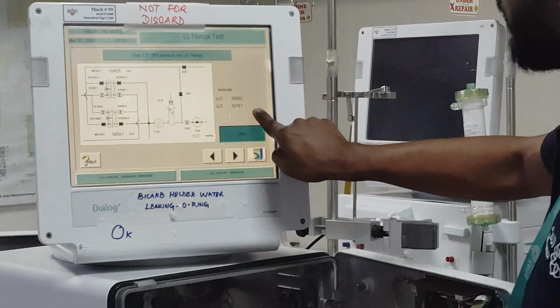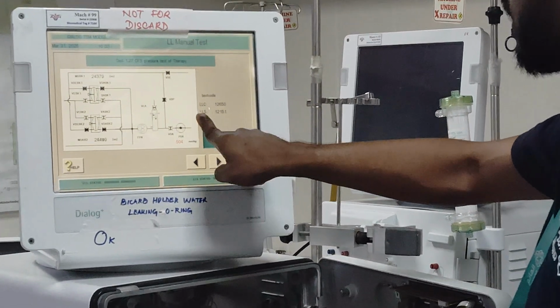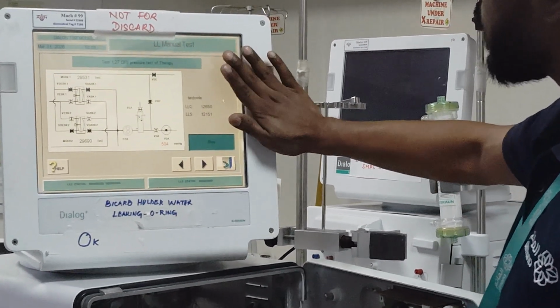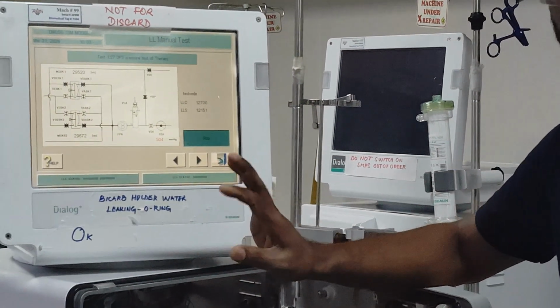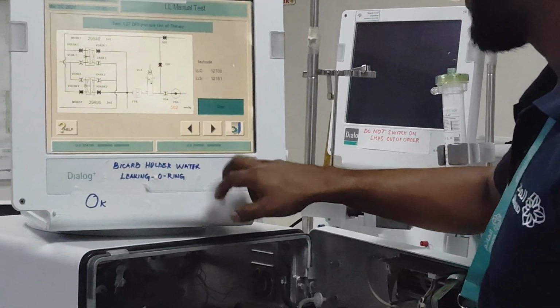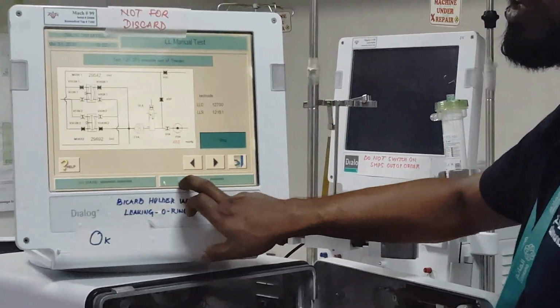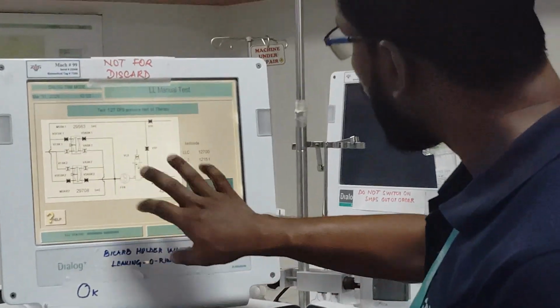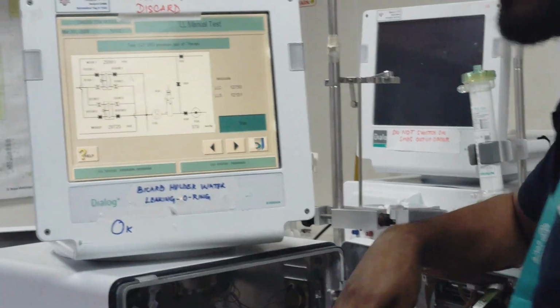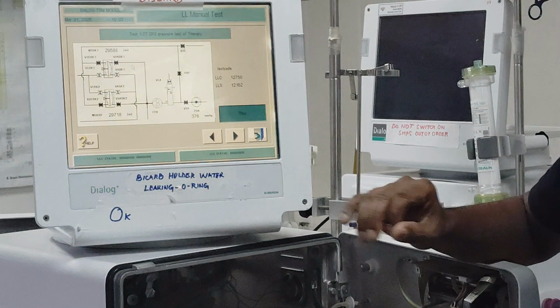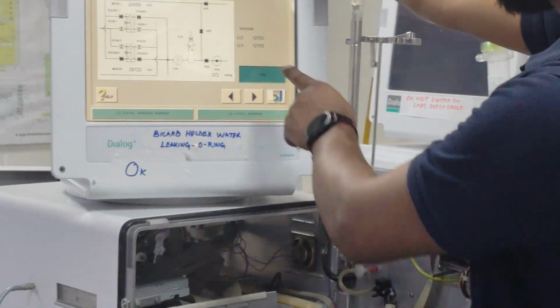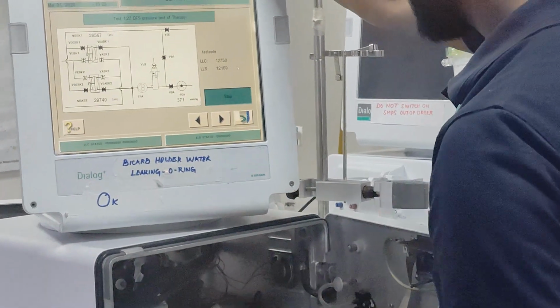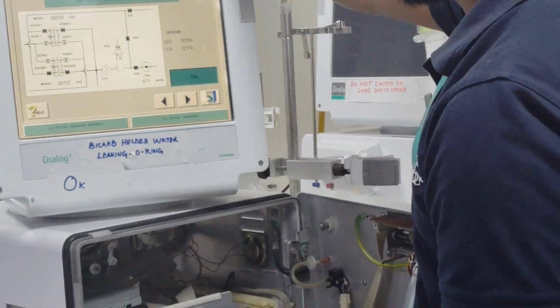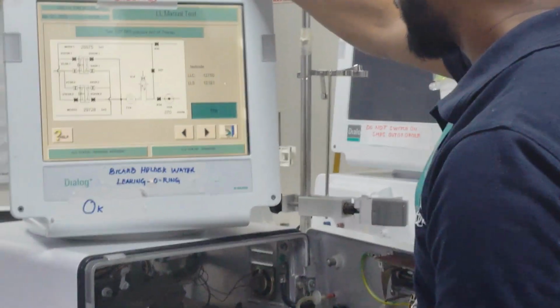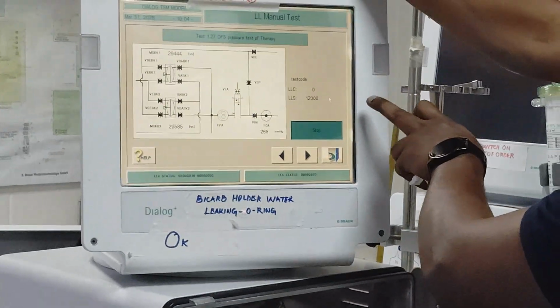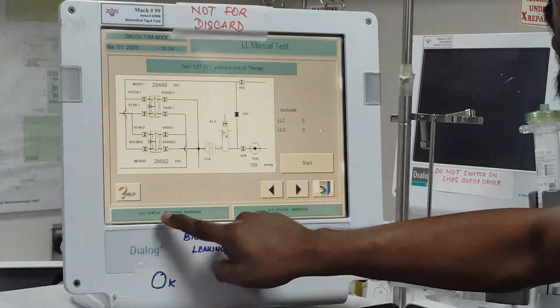After two or three tests are completed, matching with the low level controller and low level supervisor, it will check and tell us the result. Okay, your DF pressure test is okay. If it fails, it will indicate here that the DF test has failed. Then, to understand which valve is leaking, we have to check manually. Without checking, we will not come to know. So let's see what it shows now, whether it is passing or not passing. Now the test is passed. There is no error message, the test is passed.